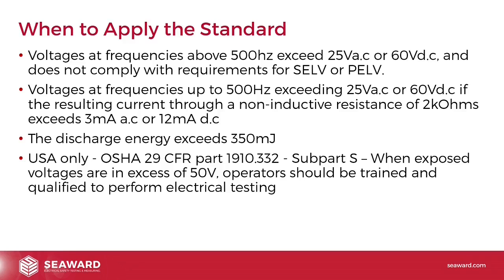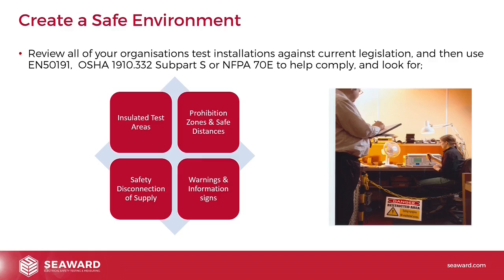And then for the USA only, they need to take into account the OSHA 29 CFR Part 1910.332 Subpart S. When exposed voltages are in excess of 50 volts, operators should be trained and qualified to perform electrical testing. The first thing we're going to talk about in creating a safe working environment is how to protect the operator.